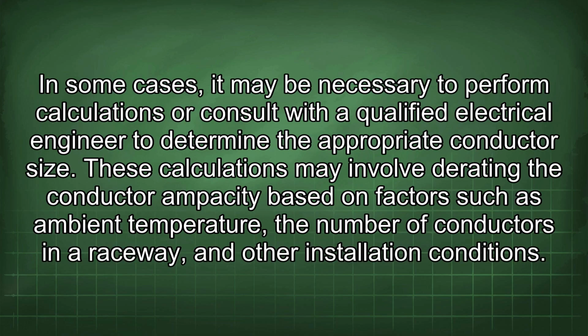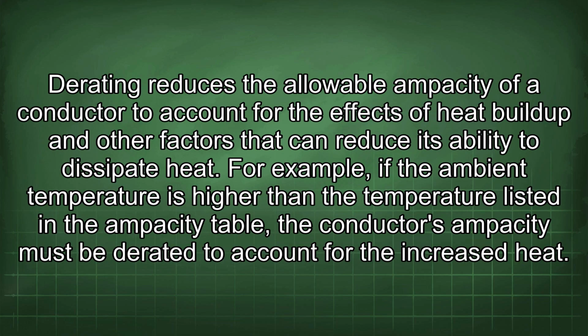In some cases, it may be necessary to perform calculations or consult with a qualified electrical engineer to determine the appropriate conductor size. These calculations may involve derating the conductor ampacity based on factors such as ambient temperature, the number of conductors in a raceway, and other installation conditions. Derating reduces the allowable ampacity of a conductor to account for the effects of heat buildup and other factors that can reduce its ability to dissipate heat.